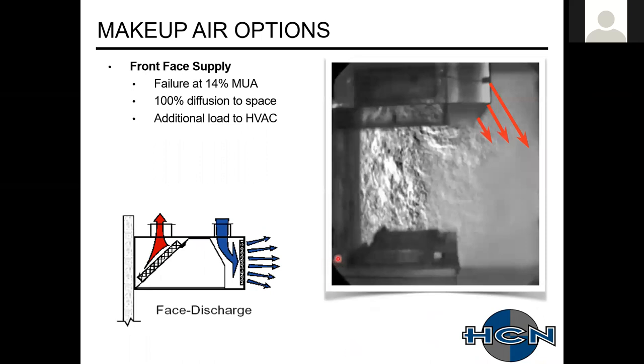After that, we came with front discharge or front supply. The air is brought into the front supply and then shot straight out. Some manufacturers had different kinds of louvers. They're not all built the same. So, some of these systems were done properly. Other vendors, depending on what kind of diffusers they were using in the front of the hood, would actually cause similar problems to what you would see with an air curtain, because if they're pointing down, that air is going to do a similar effect and it's going to get pulled right back out into the space and not work properly.